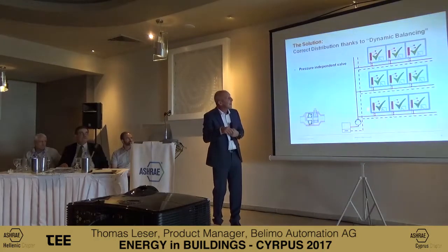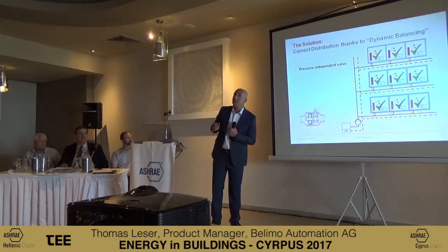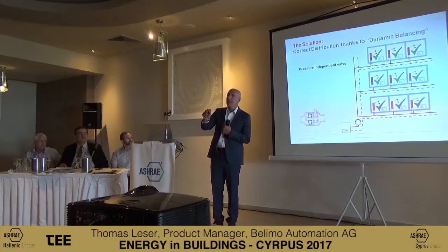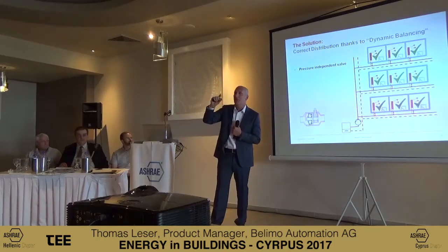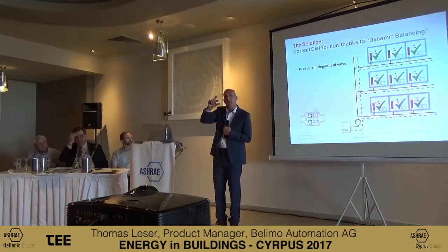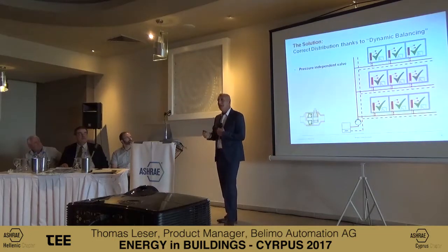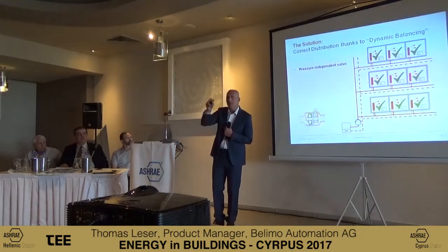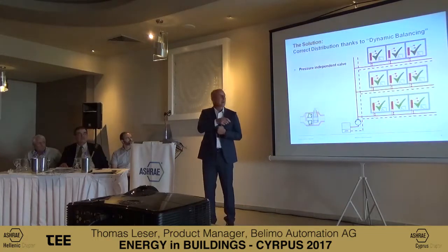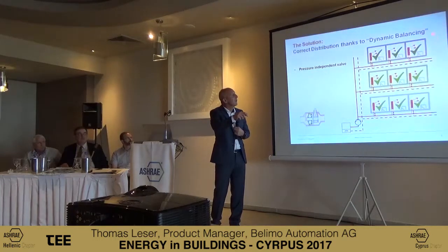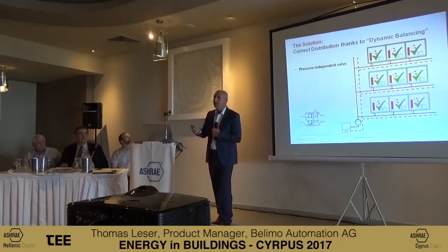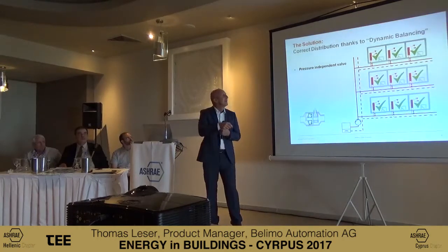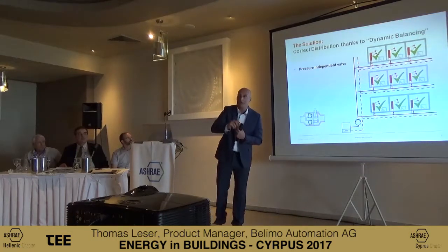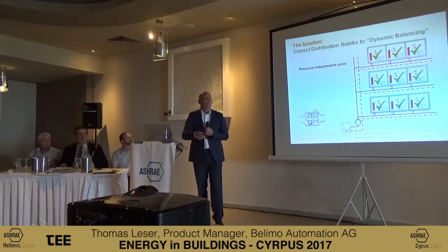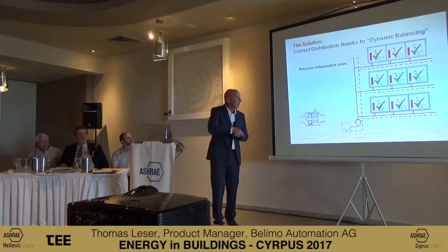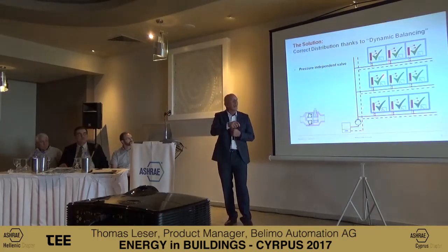And what you can do now, this is our same hotel. You just install these valves and they will adjust the flow in this pressure range. So between 15 and 400 kilopascal, once you say 5 volts, give me 50 liters, the valve will give you these 50 liters. All you have to make sure here is that the most remote installation has enough pressure. In our case, give this one 15 kilopascal, all the rest will work. That's a big benefit of these valves. Now it makes no difference if this is a constant speed pump or a variable speed pump. If this goes up and down, it will work.